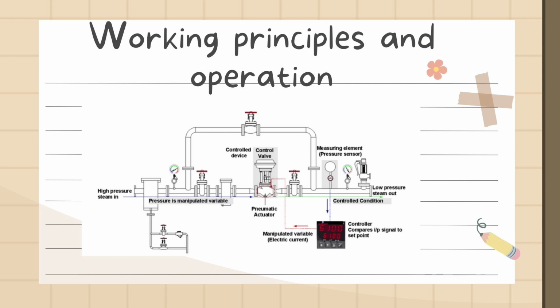Okay, so this is an example of the pressure measurement control in the food industry. This is where the high pressure steam comes in, and this is a section where the pressure is the manipulated variable. So this pressure gauge measures the pressure of the steam that enters the system, and it goes to the control device, which is the control valve. At this part, the pressure is regulated. When the pressure is too high, the pressure will be lowered and controlled here at the control valve. And then it will go to the measuring element, the pressure sensor, which is here, and it will undergo a certain part where the pressure is also controlled and the low pressure steam goes out.